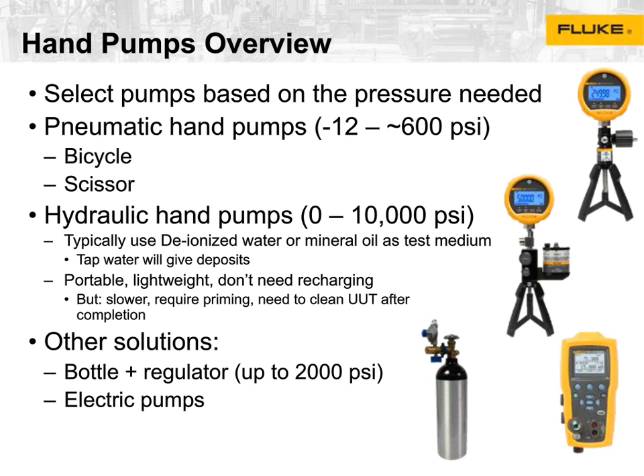Last but not least, manufacturers are starting to release electric pumps, and so I've actually got a picture of a Fluke unit here that has an electric pump built in. These are primarily the most useful at low pressures. So the unit here, for example, goes up to 300 psi. There are much more expensive units that go up to as high as 10,000 psi. So they're starting to become a useful replacement because pumping is no fun.